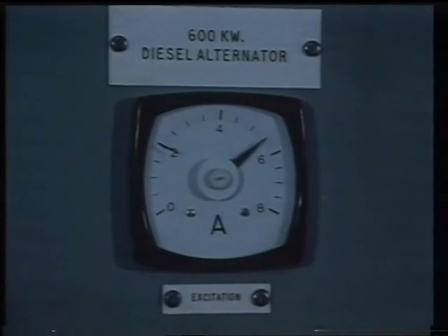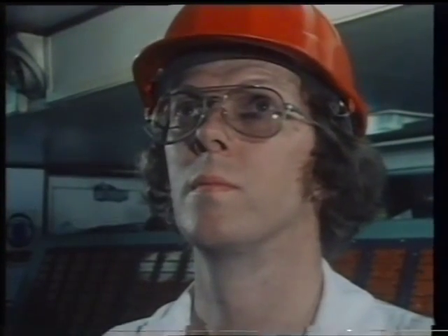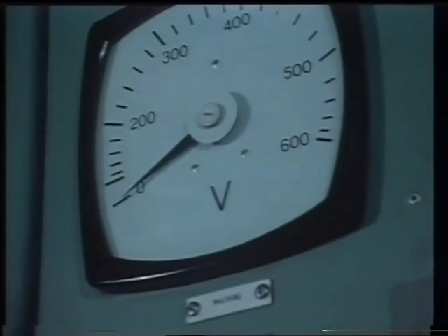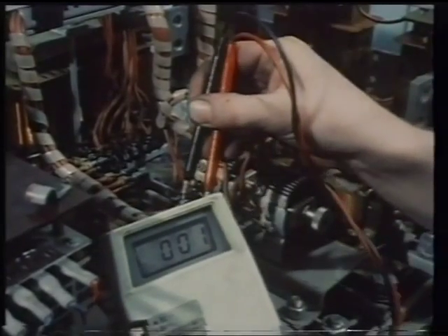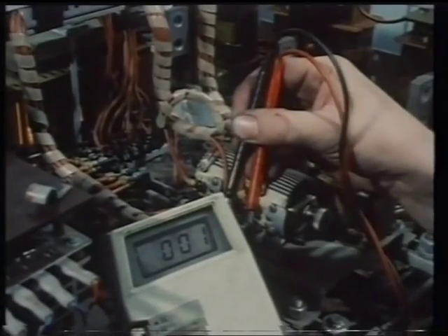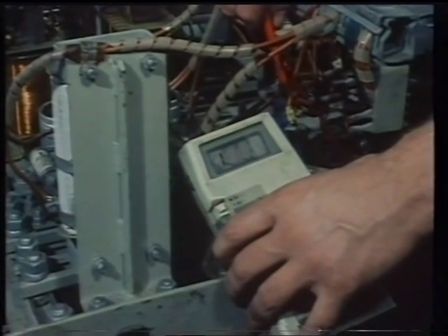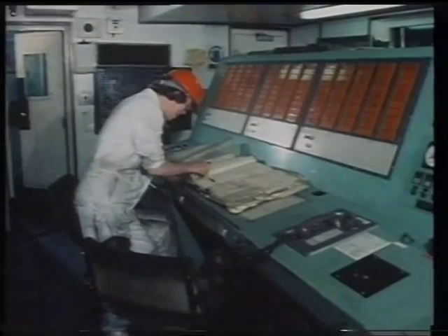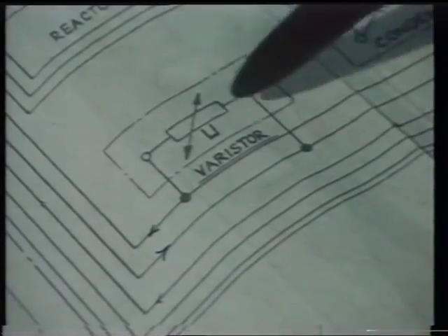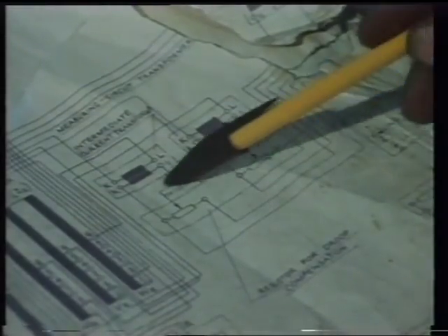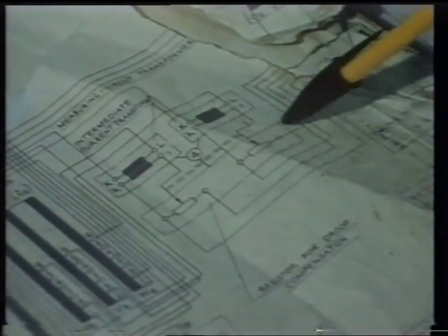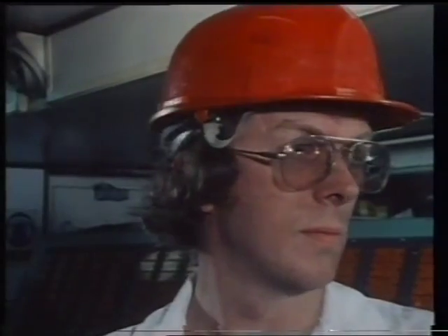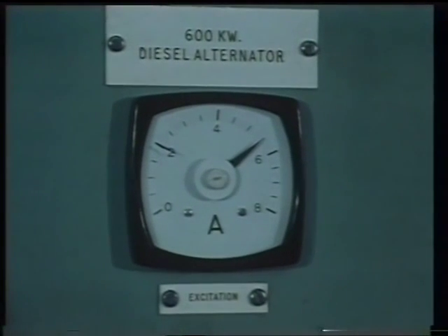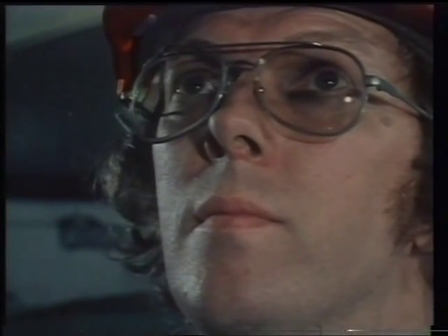If you have no meter indication of excitation, you will need to test the exciter, as shown just now. With some designs of static exciters, the check can be made at the automatic voltage regulator, after the circuit diagram has been studied. These exciters would not produce a DC output if there was no AC output. Here, the ammeter shows that the exciter current is high, very high. Yet there is no AC output.